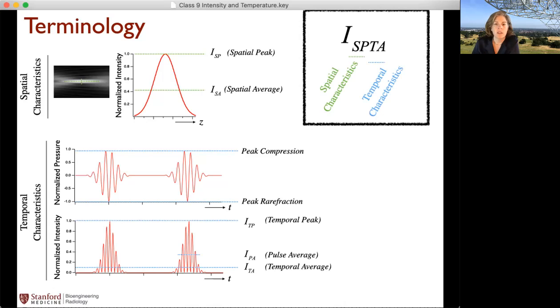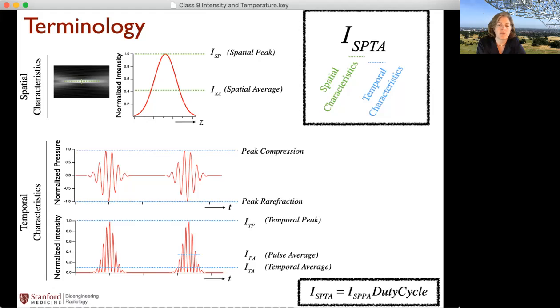All right, when we typically put them together, we'll start out with what our measurement is. So here it's intensity, or it could be pressure, but let's say it's intensity. And we'll start out with our spatial characteristics, whether it's the spatial peak or the spatial average. And then we end up with our temporal characteristics over here. So that could be either temporal peak, pulse average, or temporal average. So ISPTA is actually really important. It's the spatial peak temporal average. And what we'll see is that that one's really important for heating, which is something that we'll talk about quite a bit.